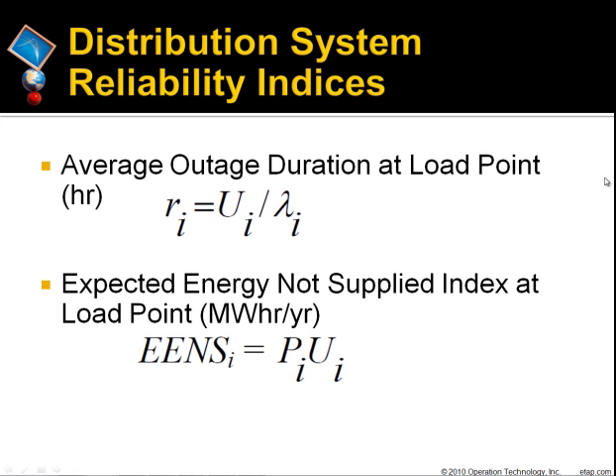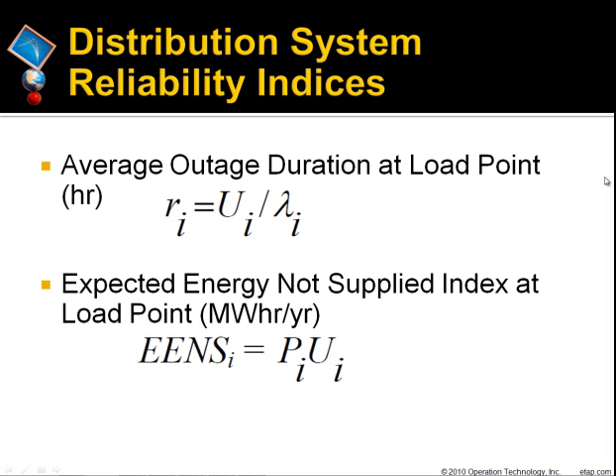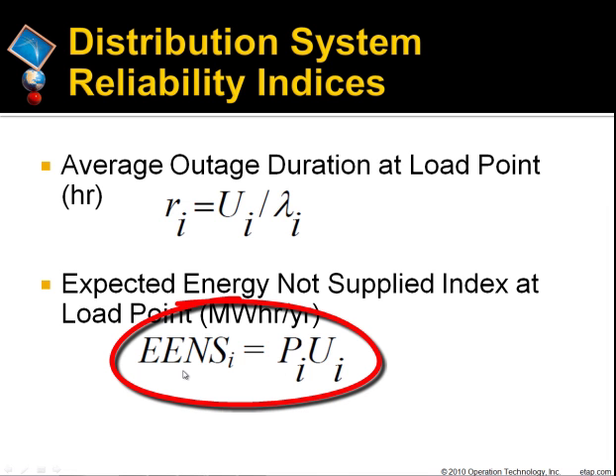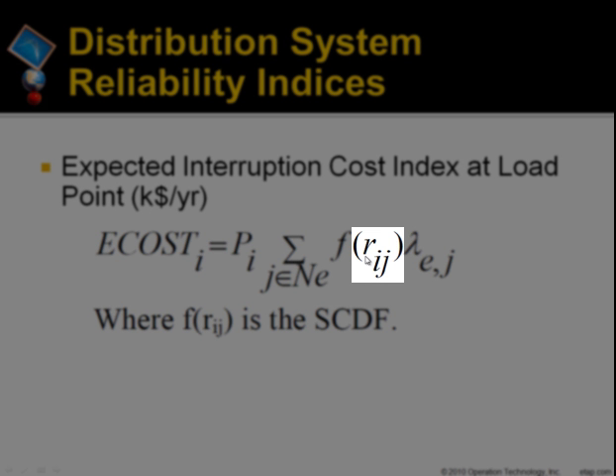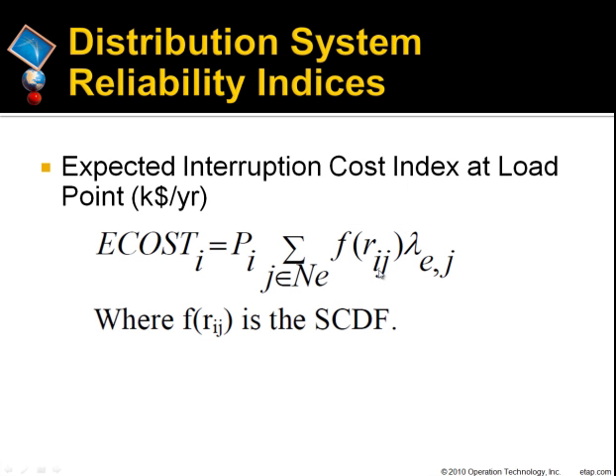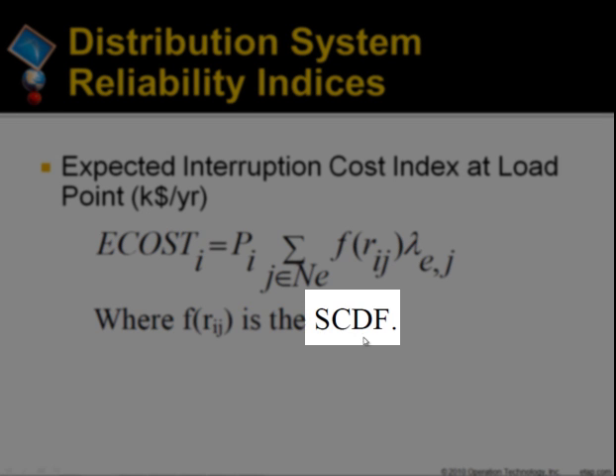The average outage duration at load point i in hours is equal to the annual outage duration over the average failure rate. The expected energy not supplied index, EENS_i, at load point i is equal to the average load of load point i times the annual outage duration. Expected interruption cost index at a load point is calculated by this equation, where the function of R_i,j is a sector consumer damage function, also known as SCDF.